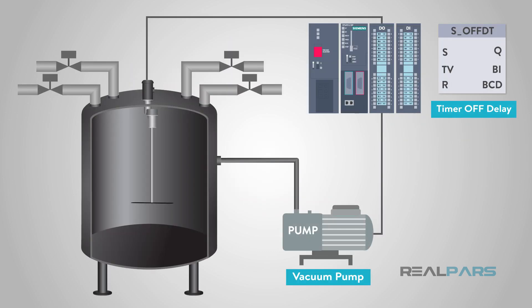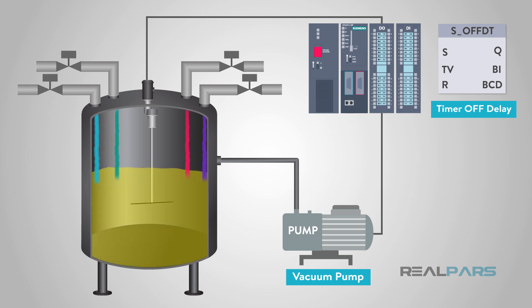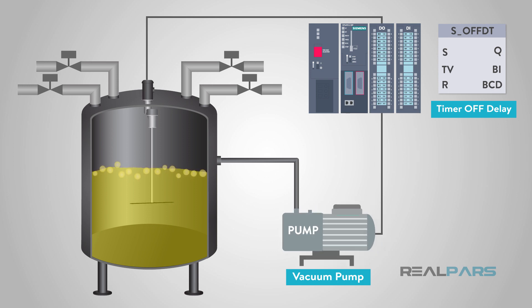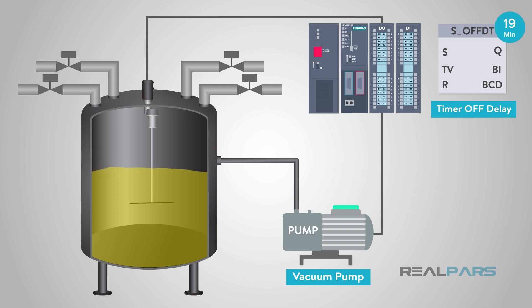Vacuum pumps are commonly programmed with off-delay timing control blocks. One example that I am familiar with is the manufacturing of adhesives. Once the adhesive is mixed with all of its ingredients, the manufacturer must remove all of the extra air bubbles from the adhesive. This is made possible with a vacuum pump. The operator will start the vacuum pump while the mixer is turning and let it run for the programmed period of time, usually half an hour or longer. Once the timing period ends, it will turn off the vacuum pump.